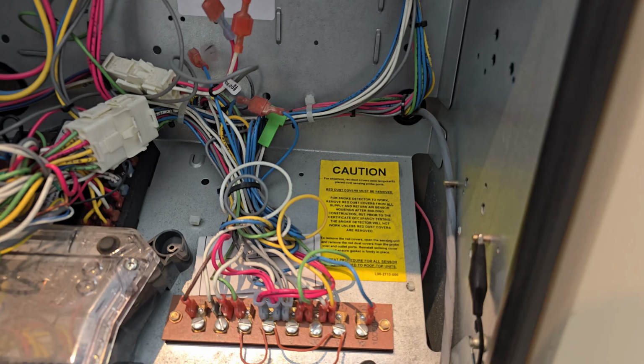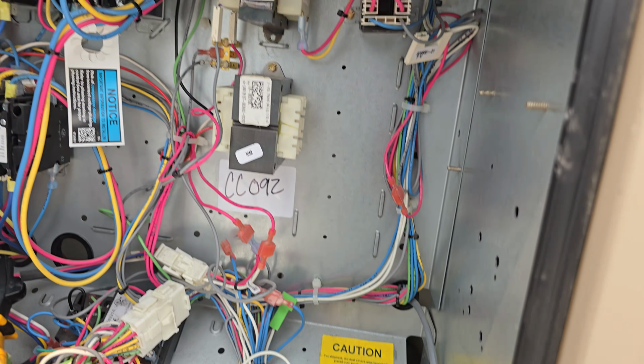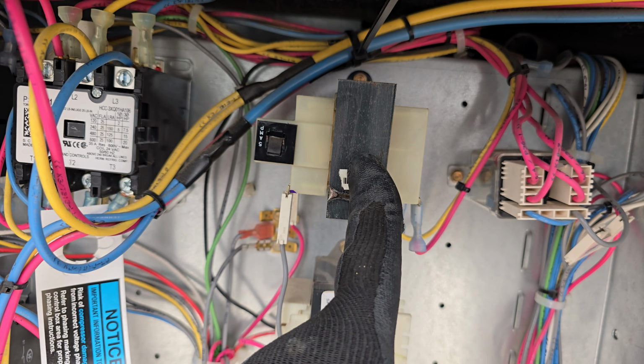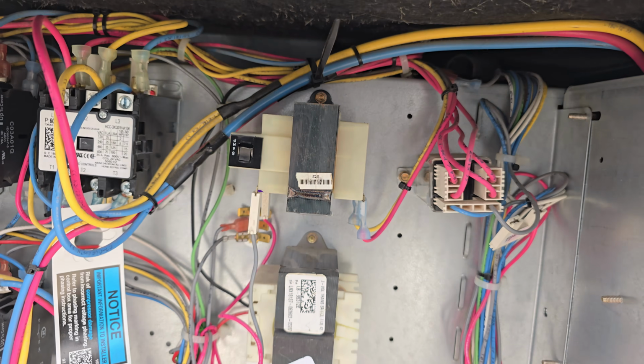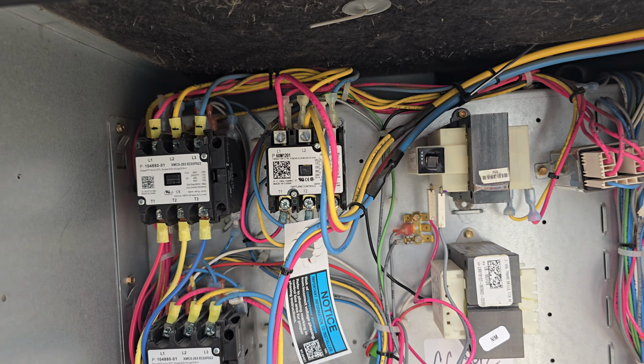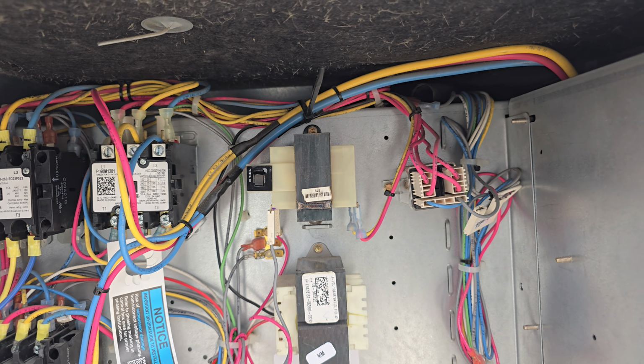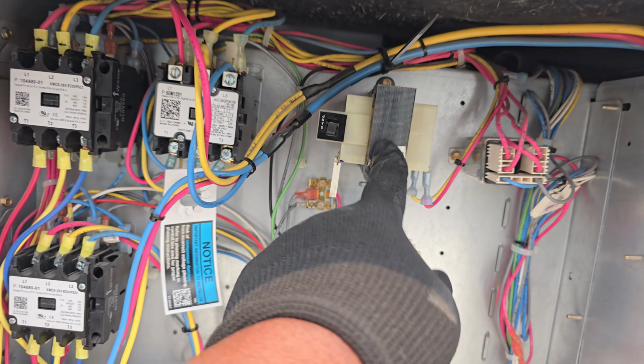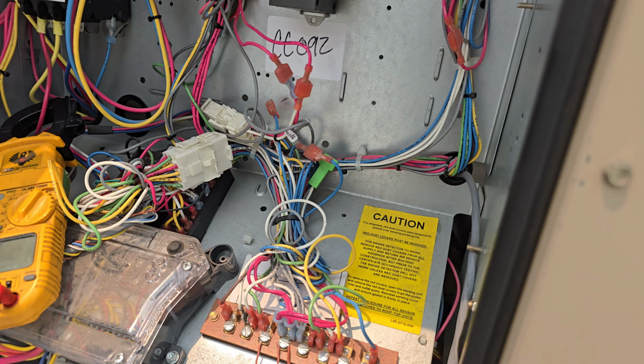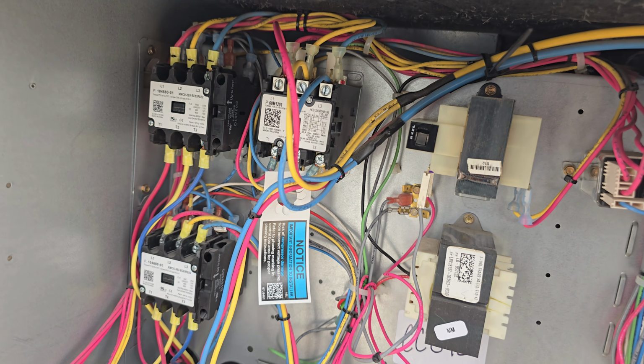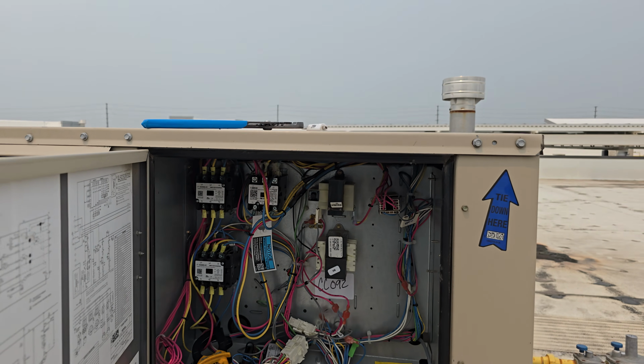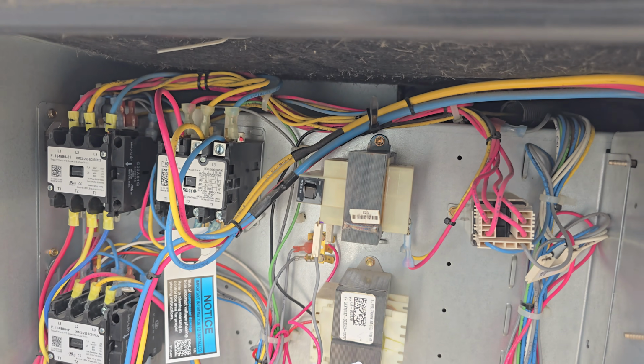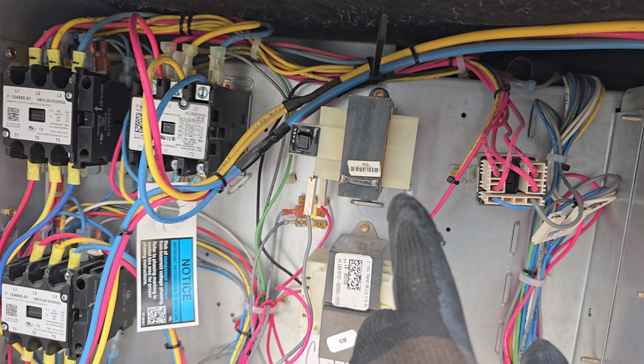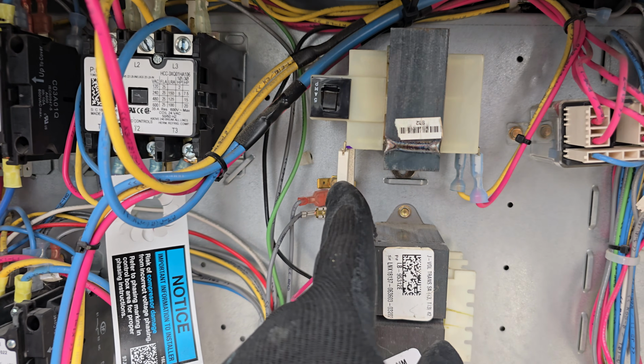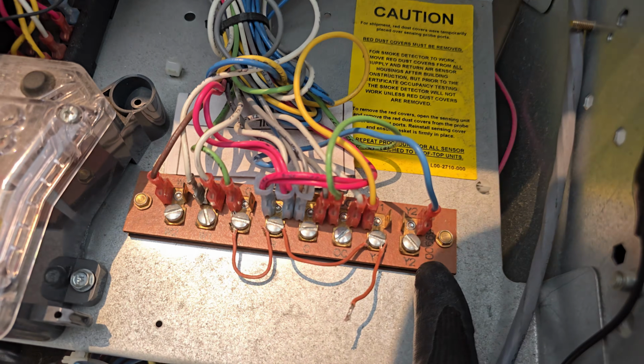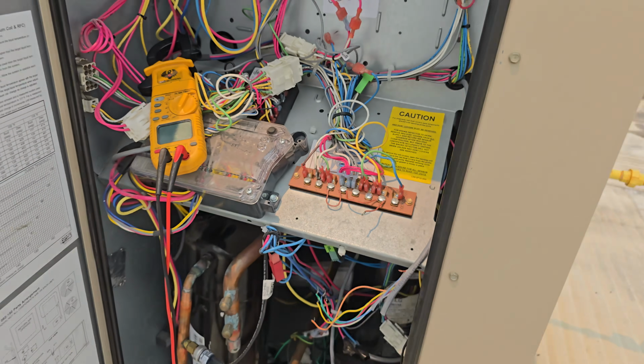Before disconnecting my Y2, I also swapped my transformer, because I was thinking it could be weak, so maybe it's not able to hold the amps. This is a new transformer, but after swapping it, I still keep tripping off. So I have also eliminated the step down transformer, 600 volt to 24 volt, as the problem. So this I'm going to see, which is my Y2, and see what's going on here.